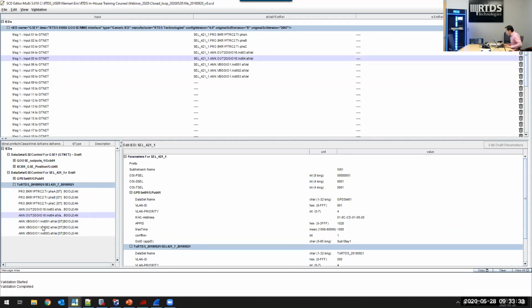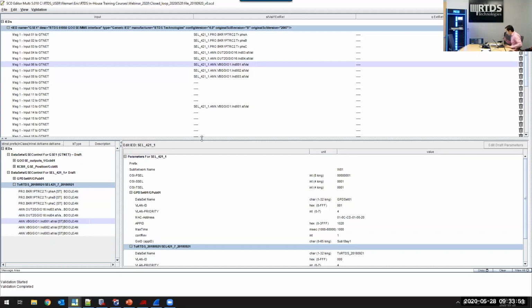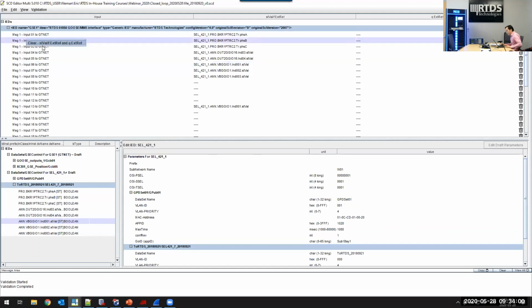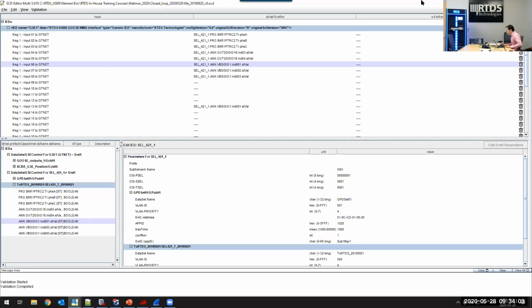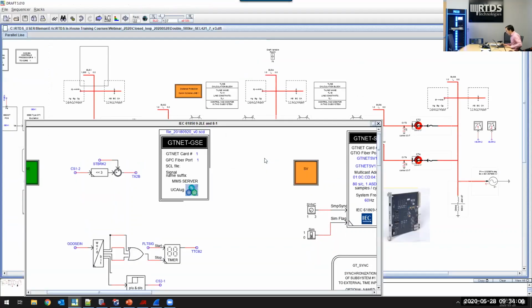Now, to associate these 5 data attributes from the relay to the GTNet Goose input, we can drag each one and drop it to a field here that corresponds to a specific input. For example, you can just easily do like this. Here we have the top 5 mapped to the GTNet inputs 1 to 5, as shown here. Next step is to see how the GTNet inputs are associated with a variable input in draft, and then to control the breaker.